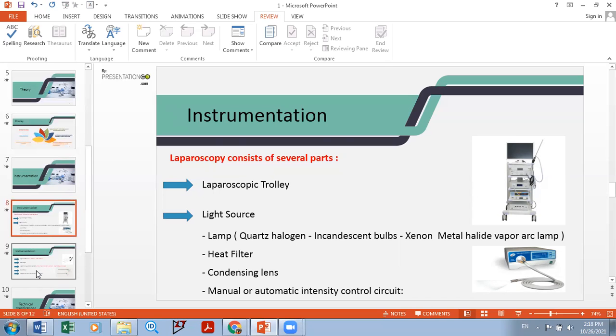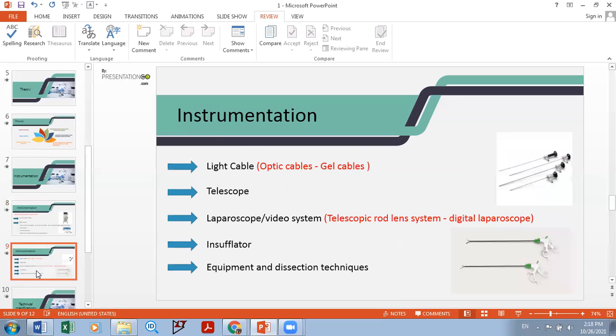The second part is the light source, which has four components. There are four types of lamps: halogen, xenon, and vapor lamps. Because the light generates heat due to infrared radiation, a heat filter is used to eliminate this heat, since it can have a bad effect. A condensing lens brings the light from the lamp to the cable. You can control the intensity of the lamp manually or automatically.